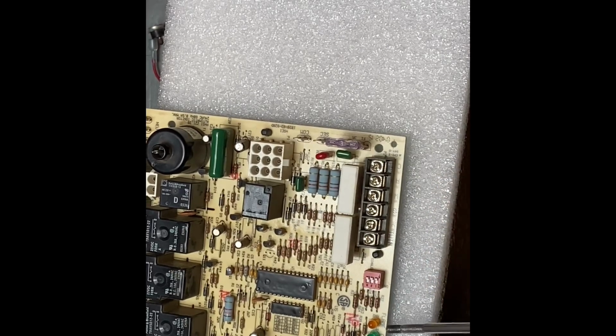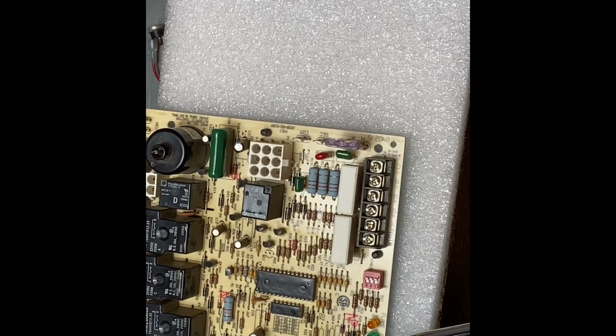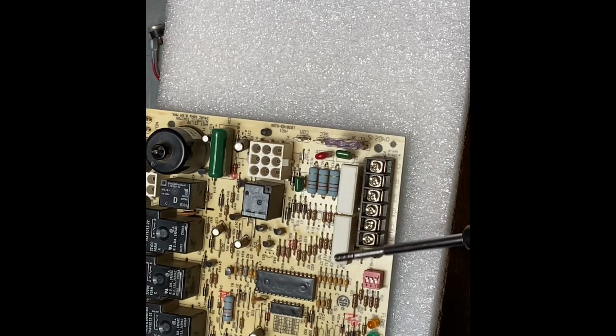Also here we have several different lights. Checking a gas furnace, the first thing you want to do is look through the little window in the door to see what kind of lights are blinking, because once you take the door off, it resets all the codes that it saved. So this is actually telling us if there's a flame, if we're okay, or if we have power. And if there's a problem, this light's going to blink so many times. Maybe it's 2 fast blinks and 2 slow blinks, or maybe it's just a steady 4 blinks in a row. There's 100 different combinations, but you have to find from the manufacturer what the blinks say, and it's going to give you an idea of what to check.